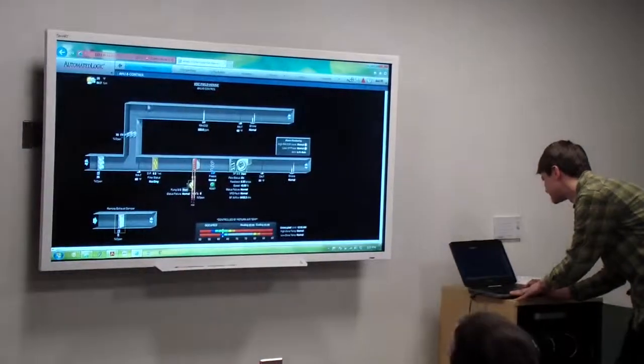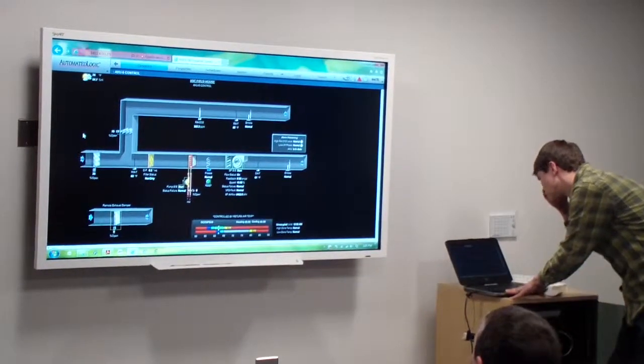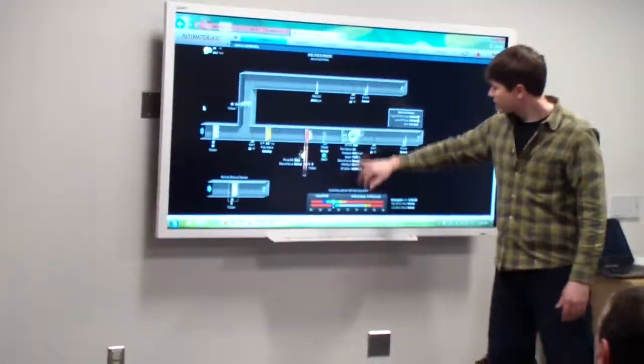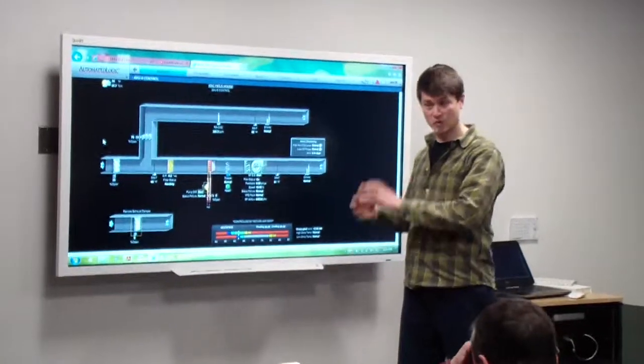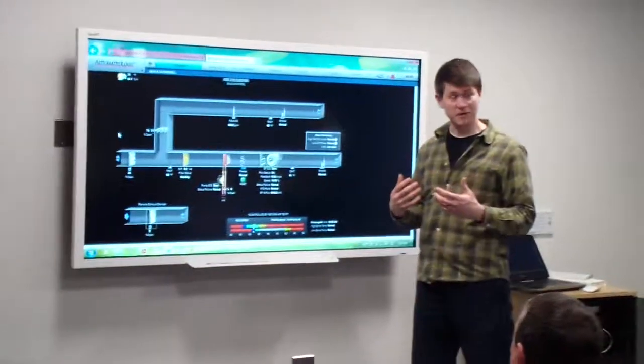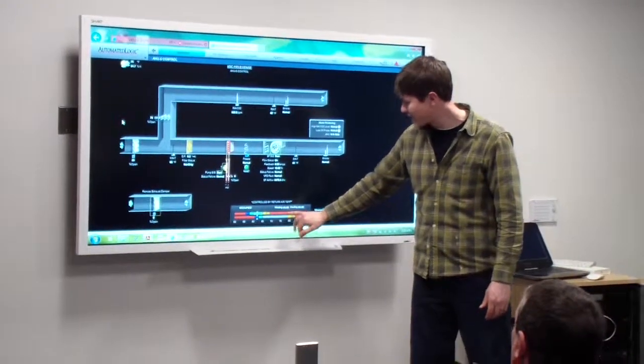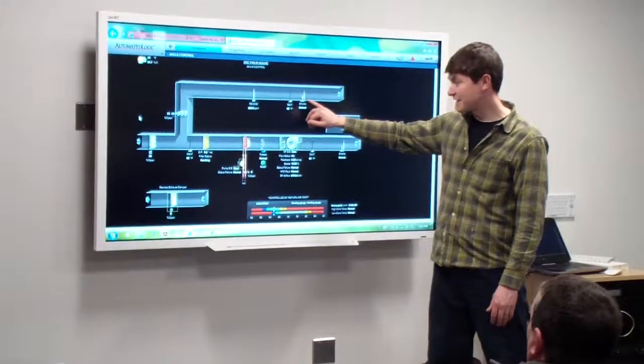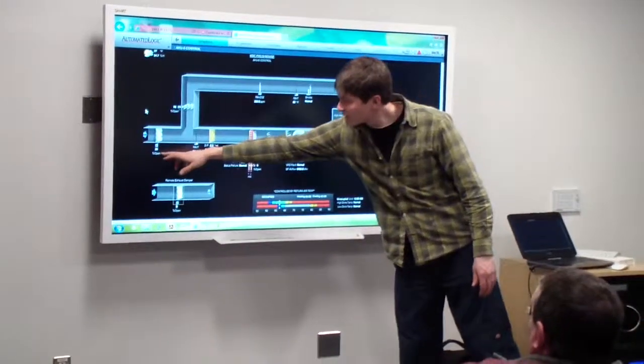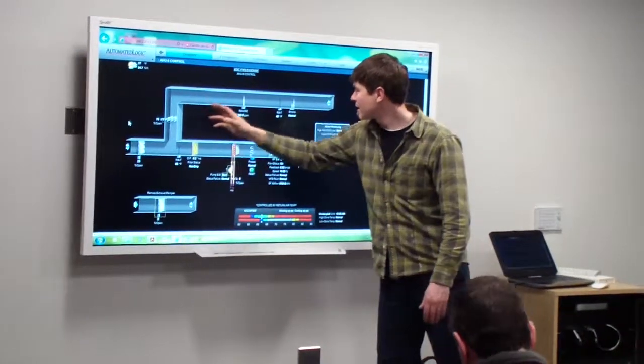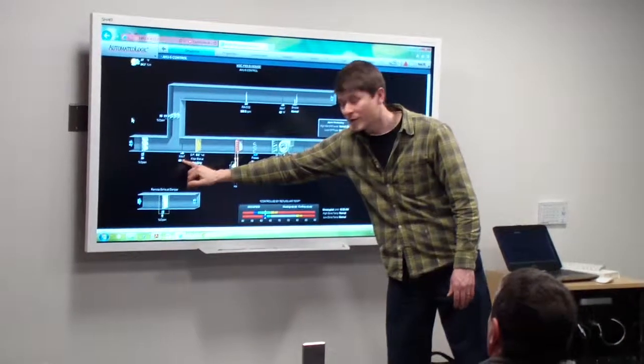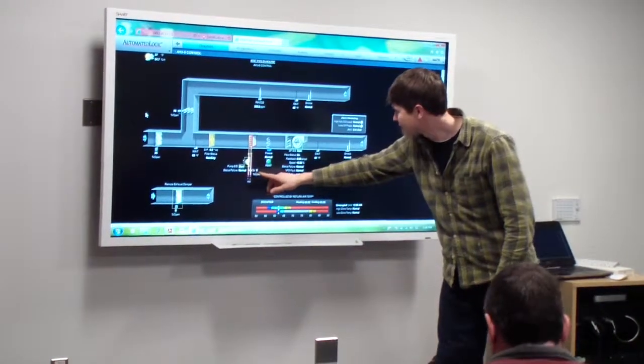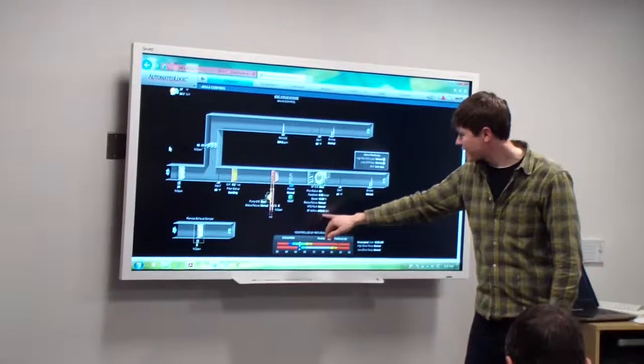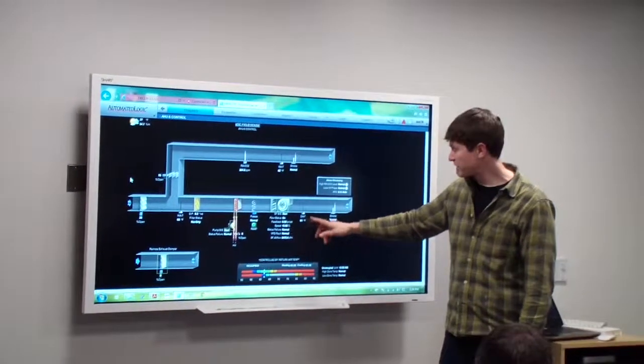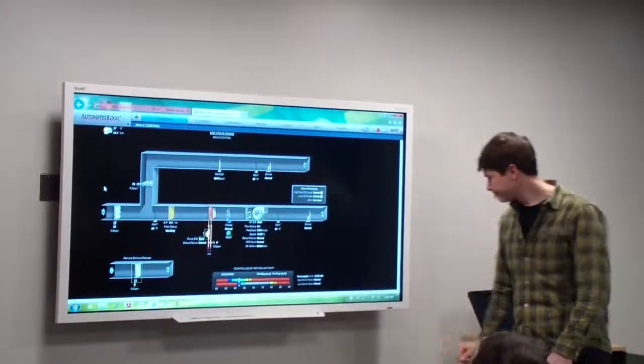I'll look at AHU5. So these are run off of their return air temp. So it's not actually a zone temp that's in there, but it's drawing the air into its return plenum, measuring what that is and trying to maintain that. So right now, they're looking for 60, we're getting 62, which I feel is pretty good. 25% outside air coming in, 75% is what it's returning through. We've got our mixed air temp at 60 degrees with the hot water valve, freeze stat for protection, and then our CFM to know what we're registering for airflow. We're discharging 61 degrees into the space. Does that seem like a good temperature out there?